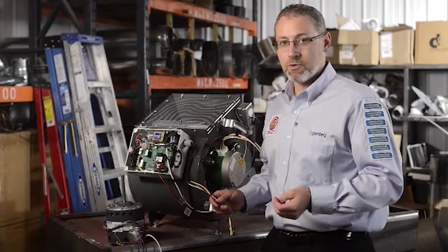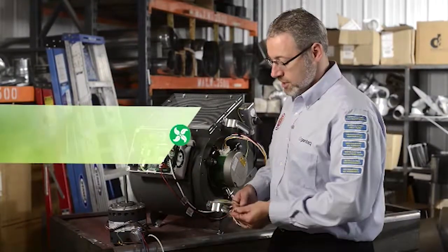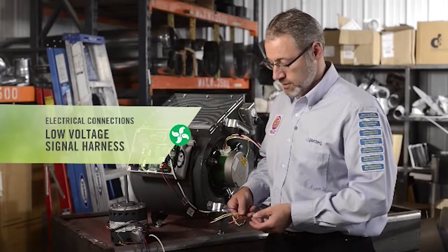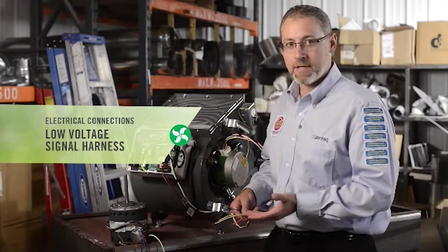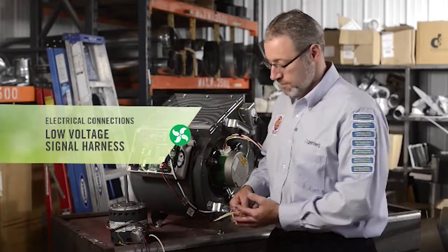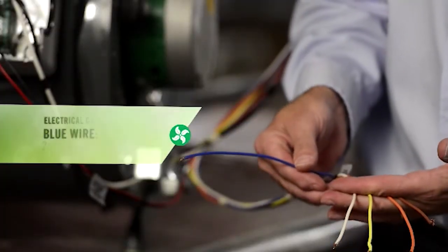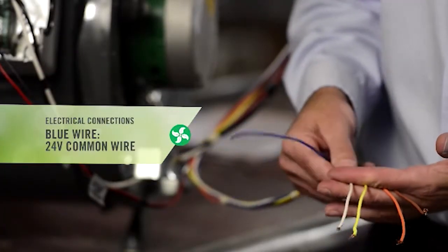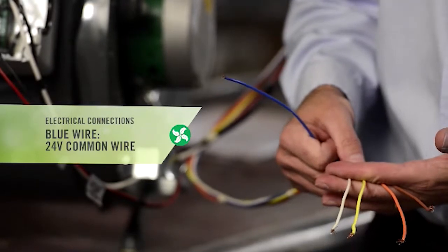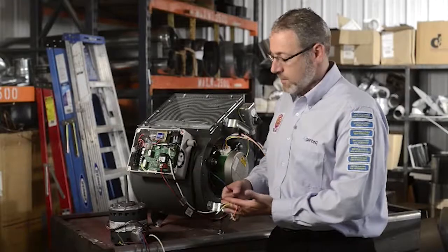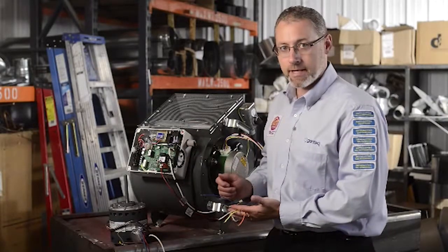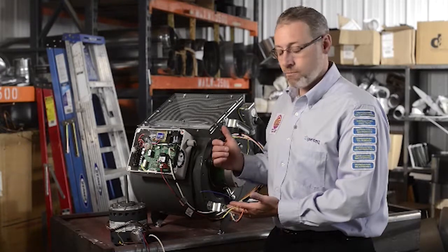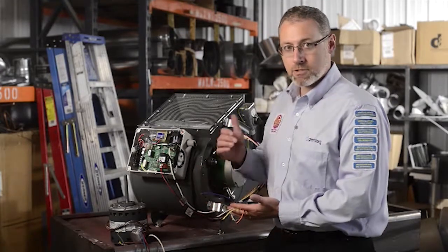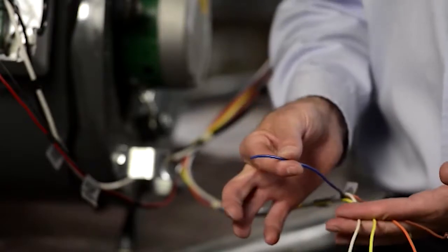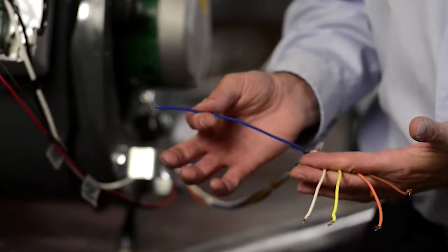we've already connected 2 of the 3 harnesses. The last harness is what we call the low voltage signal harness. These are actually the speed taps of the Evergreen IM motor. The blue wire is a 24 volt common wire. The other 4 wires are our 24 volt speed taps. And we're going to connect those to the thermostat connections to make sure we have whatever speed we want match the demand. So for example, the blue wire would go to our thermostat common.